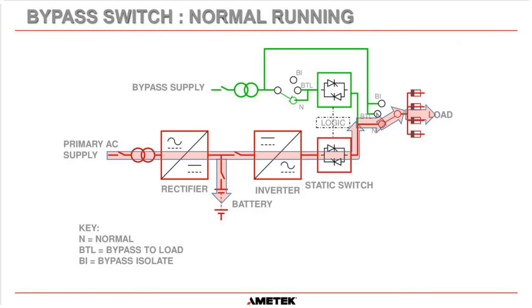So that's all the different types of topologies you're going to find for UPSs, how they're connected together. There's really only the four main ones: a single UPS, a parallel redundant UPS, a dual UPS using the loads as the parallel connection, and a cascade UPS.